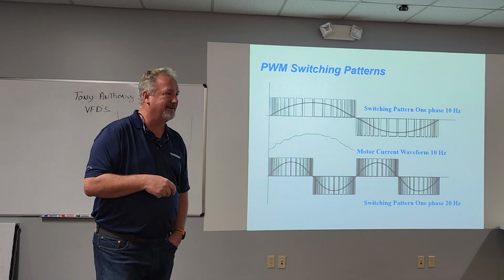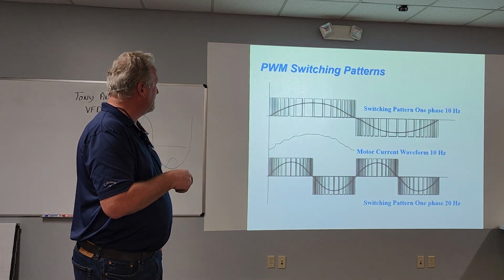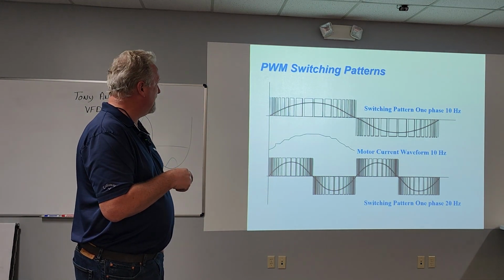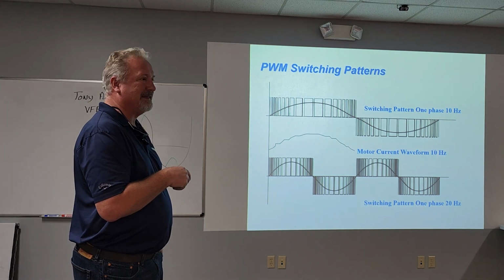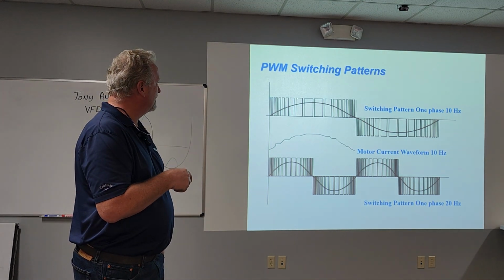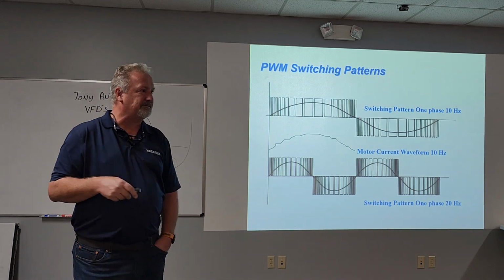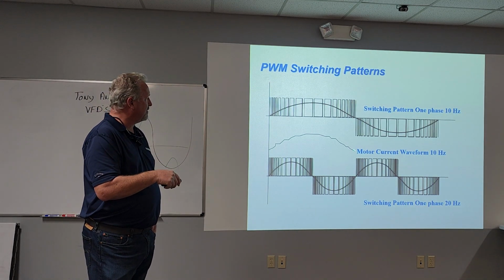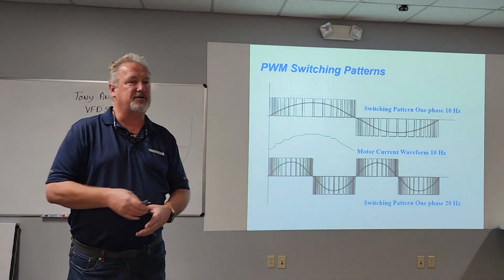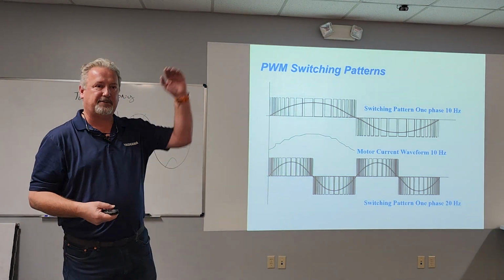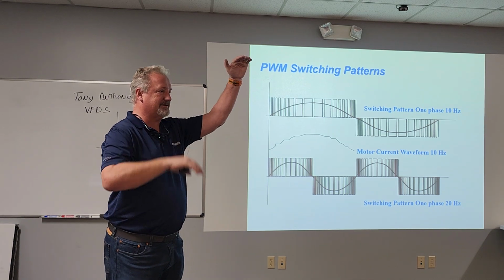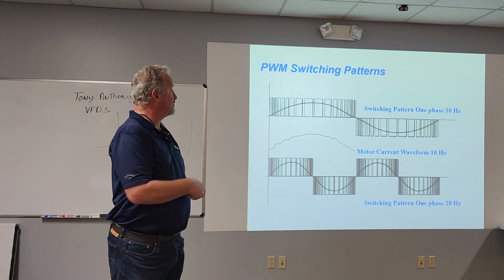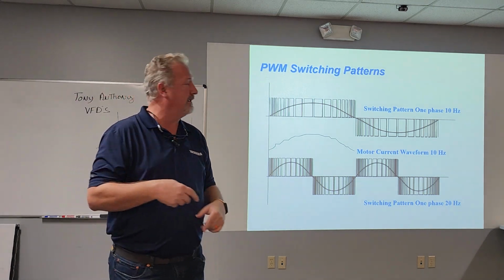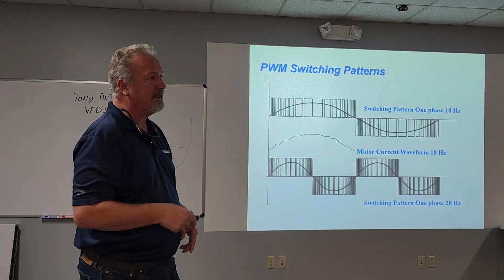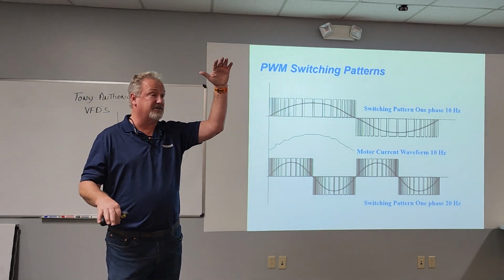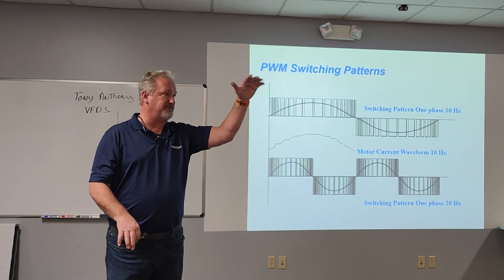The way DC works, that ain't what really happens. We turn that on, it spikes up, then drops down and then holds open. Spikes up, kind of like that inrush current on the AC, remember? Spikes up, comes down, then holds, spikes up. So actually, the peak spikes are here and down here. They're hot, they're more. So if you're running a motor on an across-the-line starter, your peak-to-peak voltage, if it's 460, is 460 to minus 460, that's 920. On a drive, because we're pulsing that DC out to it, and it's spiking up and then holding, those spikes, that pulse could be 1200 volts right by the drive.